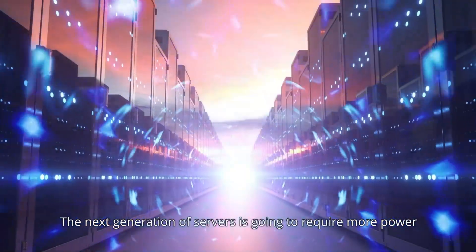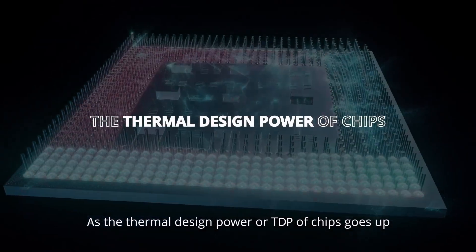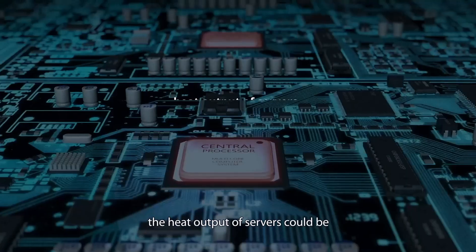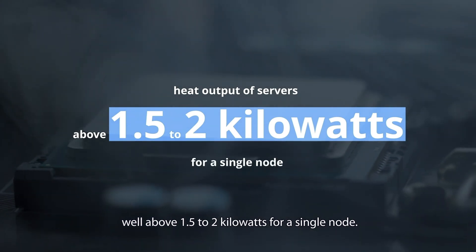The next generation of servers is going to require more power as workloads push the latest chipsets and accelerators to their limits. As the thermal design power or TDP of chips goes up, the heat output of servers could be well above 1.5 to 2 kilowatts for a single node.